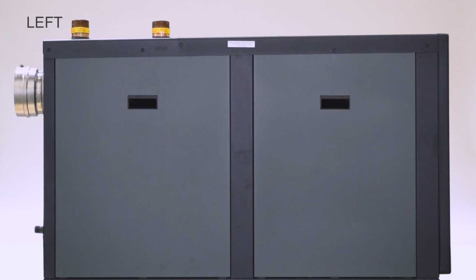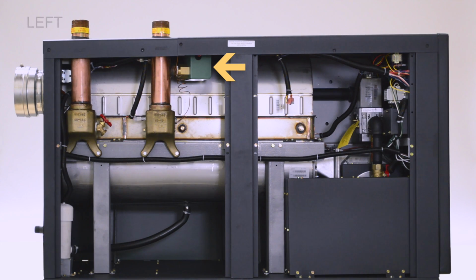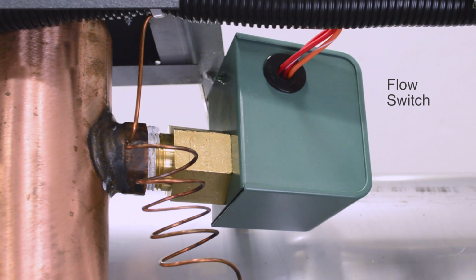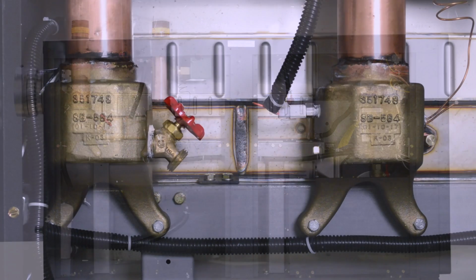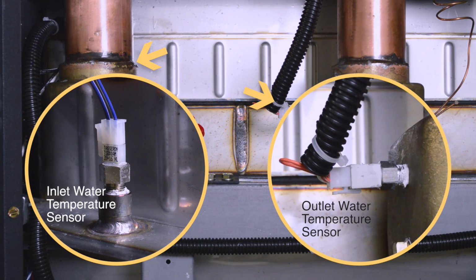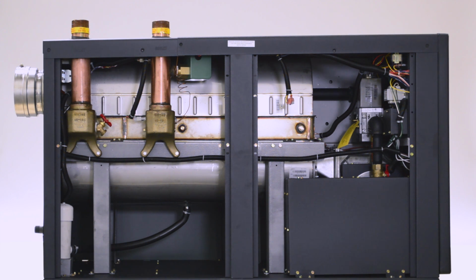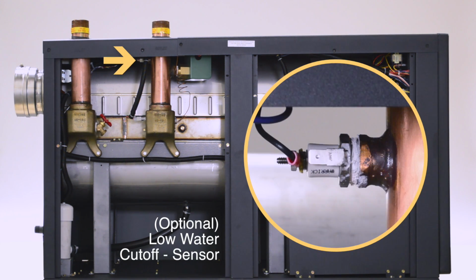Located on the left side of the unit, the flow switch, which verifies flow through the heat exchanger. Inlet and outlet water temperature sensors. Your unit may have an optional low water cutoff. The low water cutoff sensor confirms no air is present in the heat exchanger.